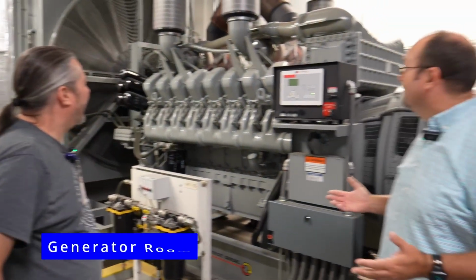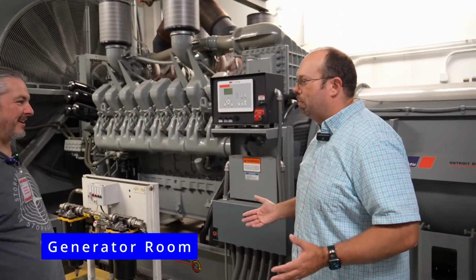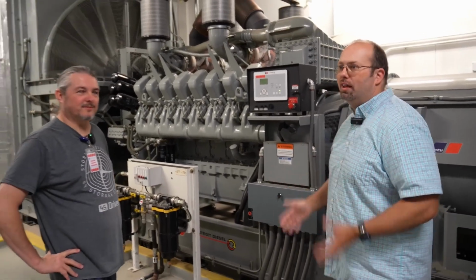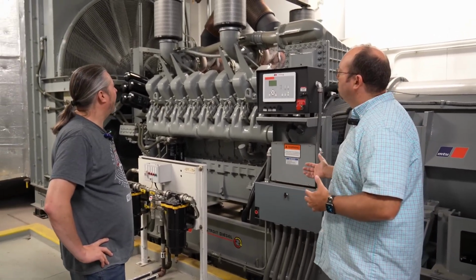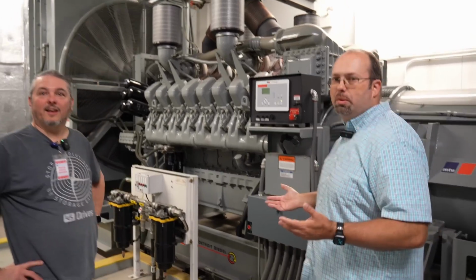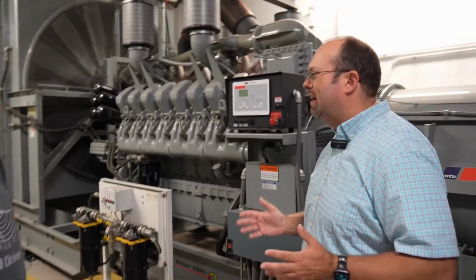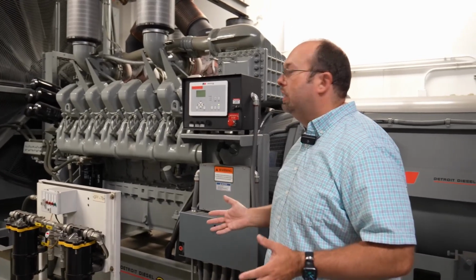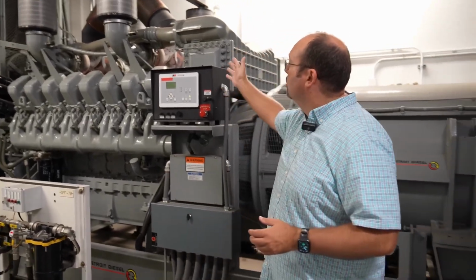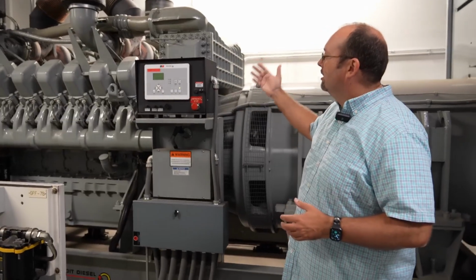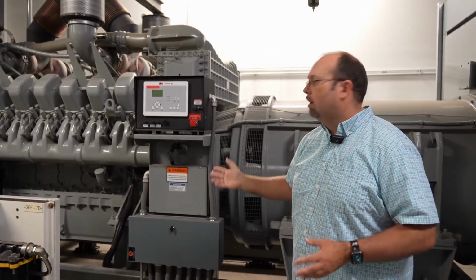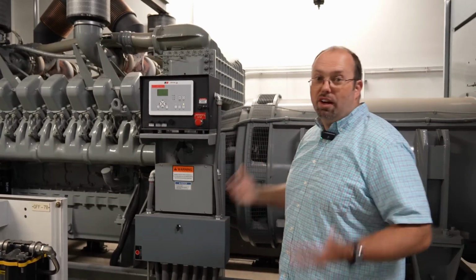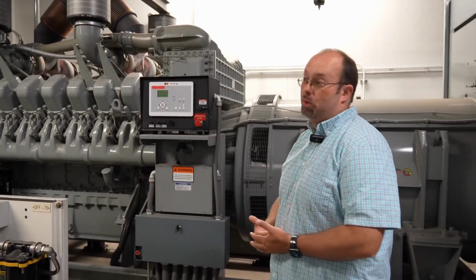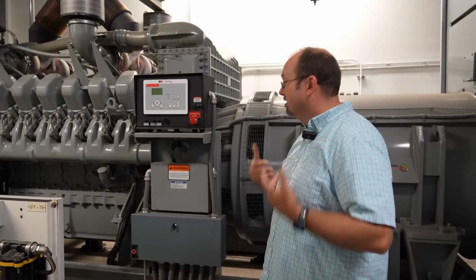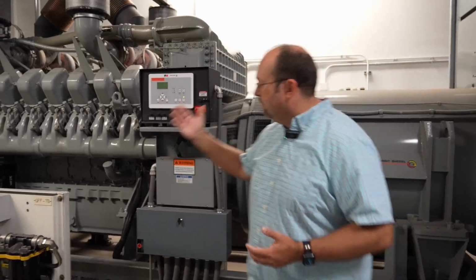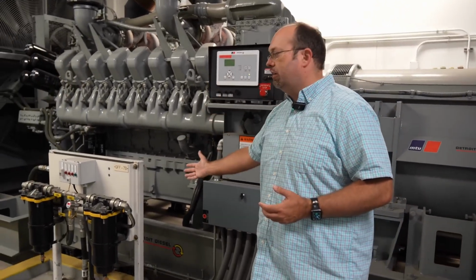So what we're looking at is the diesel generator backbone of a data center. Power goes out, this is ultimately what kicks on to provide power for the building. They range in size from about 500 kilowatts up to about 2.5, 3 megawatts apiece. In this case, this unit has 4 turbos on it, allowing it to generate a massive amount of horsepower. But what's really cool is the level of redundancy built into this. You have dual starter motors, so that if the starter motor has an issue, there's a secondary one ready to go. You have fuel filtration systems next to the generators ready to go.